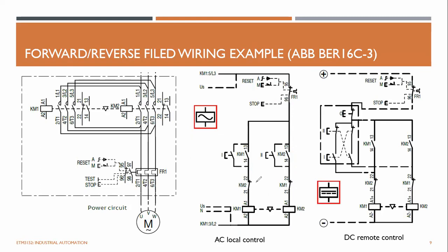At the same time, there's the electrical interlock, which means you can see in the previous case, when this one is pressed, KM1 is energized. KM1 energized means you can see the KM1 has a normally close contact, right? So it is wired here, which means if you start from this direction, this one will open, right? This one will be open, which means not allowing this to operate. Even if someone accidentally tries to close this one, it has opened and is not allowing the KM2 coil to energize. It's an interlock.